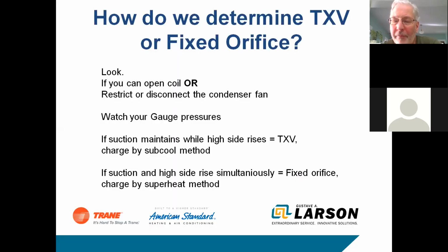And if you're not sure if it's a fixed orifice or a TXV, there's a really simple way to do it. Restrict the condenser fan. If the suction maintains while the high side rises, it's probably a TXV, because the TXV is going to try to maintain the same superheat no matter what the head pressure does. If the suction and the head pressure rise simultaneously together, it's probably a fixed orifice, and then you charge by superheat. Okay. If you can't see the TXV or the metering device, that's a simple way to kind of see what's going on.